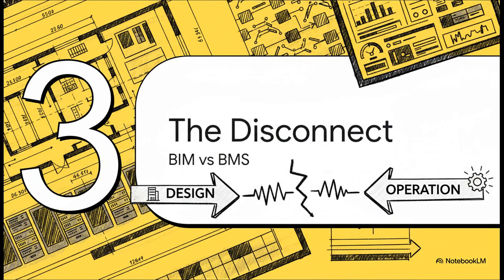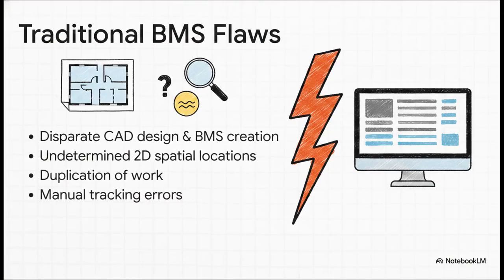Moving right along to Section 3, the disconnect between BIM and BMS. Now, if monitoring is so crucial, why are so many facilities struggling to pull it off? Well, it essentially comes down to a clash between how they're built and how they're operated. Traditionally, a data center is designed using a 3D Building Information Model, or BIM. But then, for day-to-day operations, they create a totally separate 2D Building Management System, or BMS. So you have one engineer drawing a diagram and somebody else manually typing those exact same parameters into a completely different system. It's a total duplication of work, crucial spatial data gets lost, and honestly, it just leads to major tracking errors.